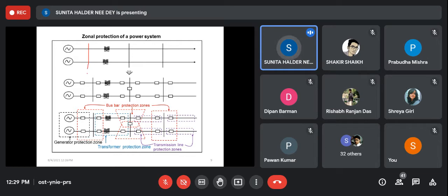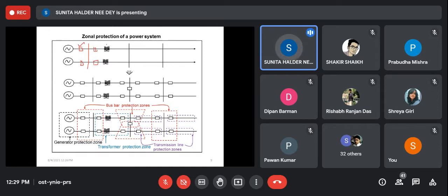This we may call the generator bus bar. Then on both sides of the generator we provide protection. Why? Because the fault may be on the generator side, or the fault may be on the transformer side. So if the fault is on the generator side, then the opening of this relay is sufficient. Then this transformer may get connection through this generator. Otherwise, if the fault is in this transformer, then obviously we should disconnect the line. So always there must be subdivision of each zone.